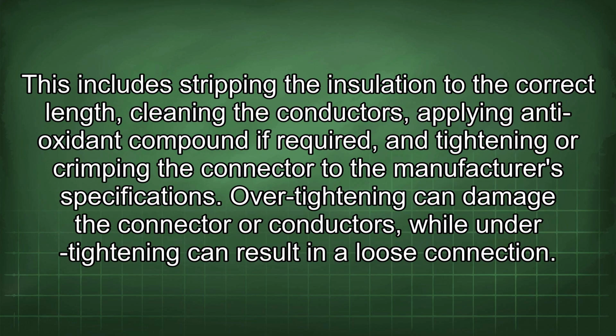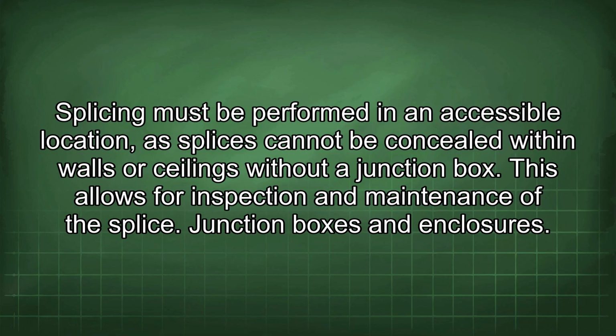This includes stripping the insulation to the correct length, cleaning the conductors, applying antioxidant compound if required, and tightening or crimping the connector to the manufacturer's specifications. Over-tightening can damage the connector or conductors, while under-tightening can result in a loose connection. Splicing must be performed in an accessible location, as splices cannot be concealed within walls or ceilings without a junction box. This allows for inspection and maintenance of the splice.